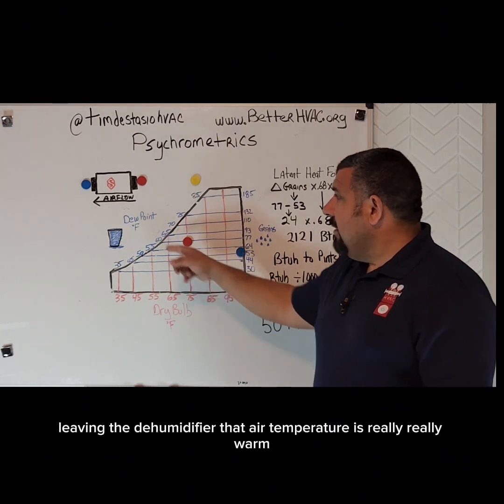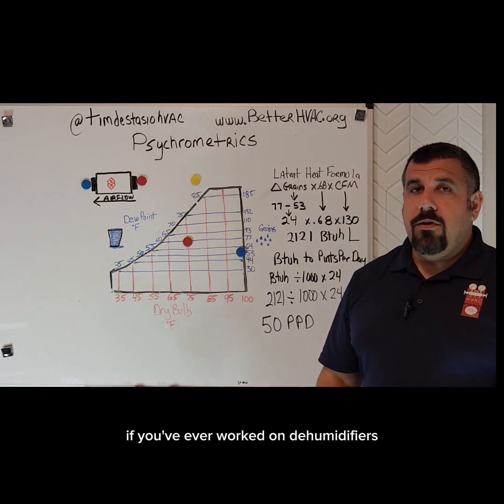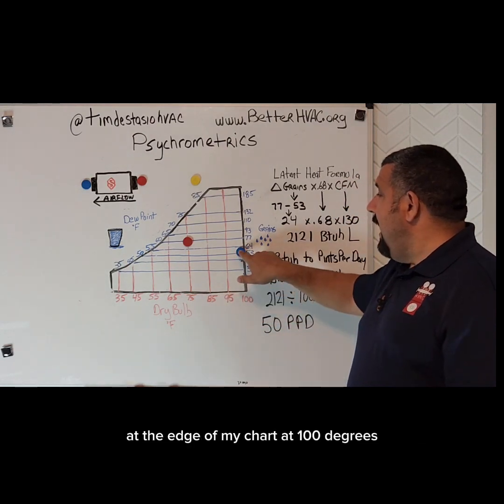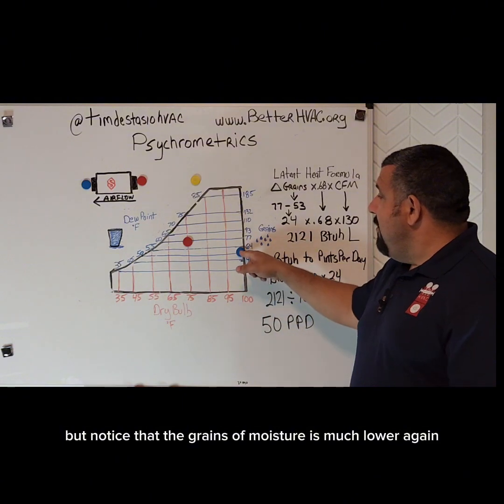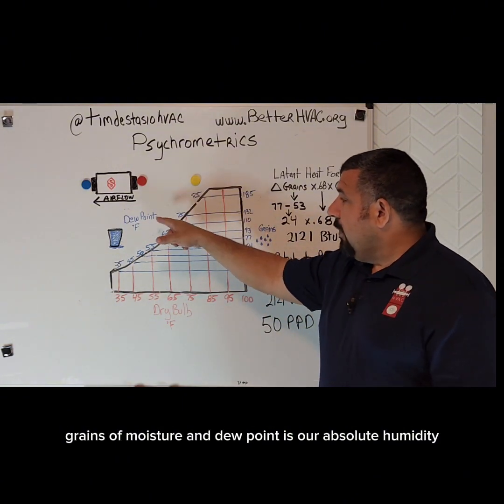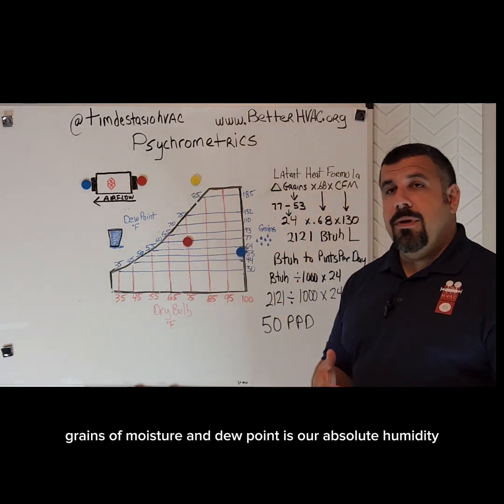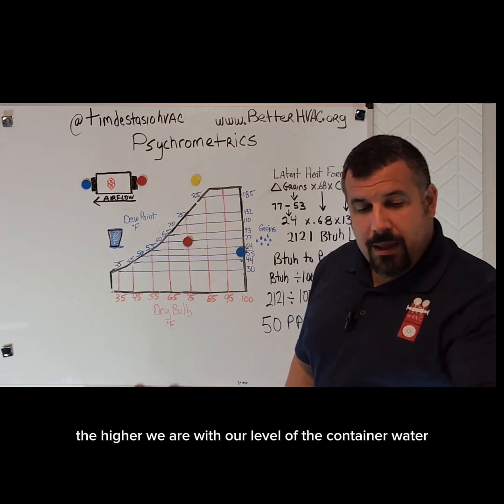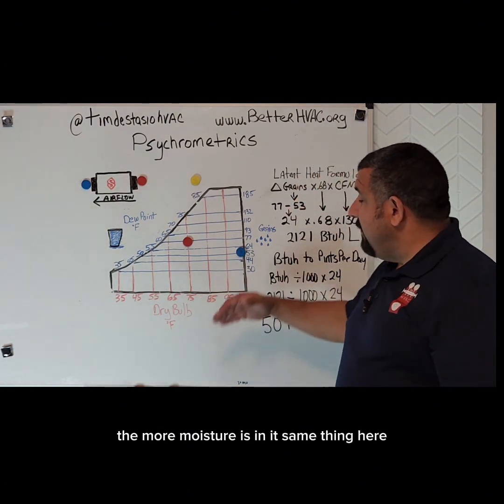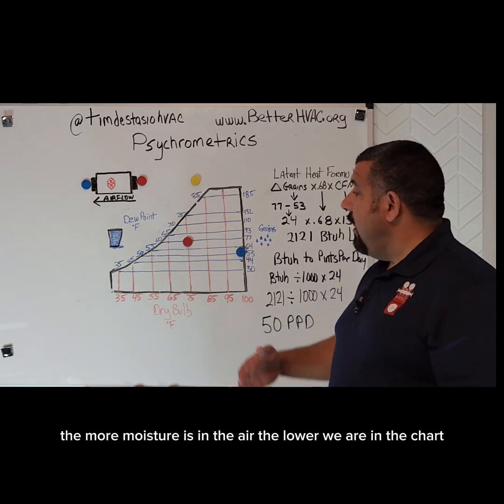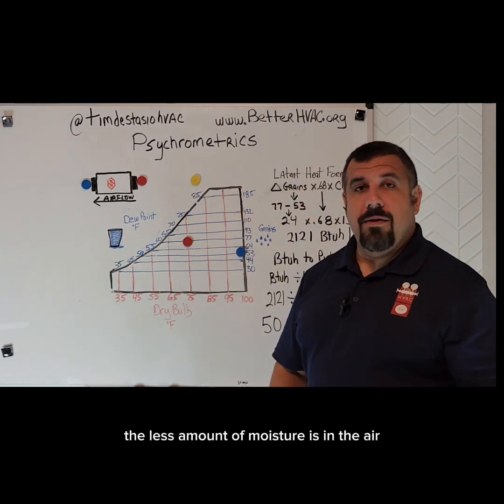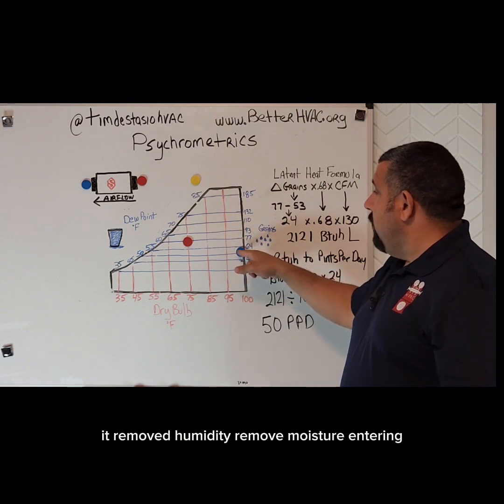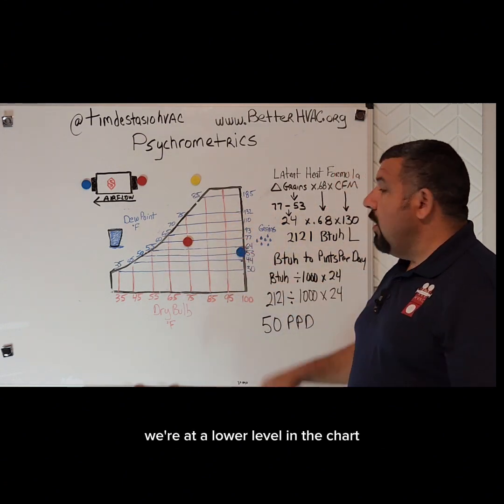Leaving the dehumidifier, that air temperature is really, really warm. If you've ever worked on dehumidifiers, you know that they put out hot air. So my dry bulb temperature is going to be way up here at the edge of my chart at 100 degrees. But notice that the grains of moisture is much lower. Grains of moisture and dew point is our absolute humidity — like having a container of water. The higher the level, the more moisture is in it. The higher we are in the chart, the more moisture is in the air; the lower we are, the less moisture. So our dehumidifier is doing its job — it removed humidity and moisture.